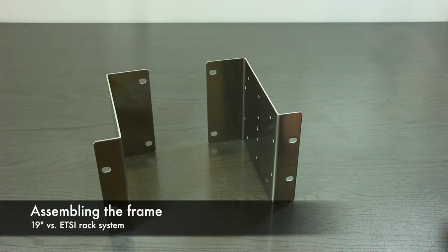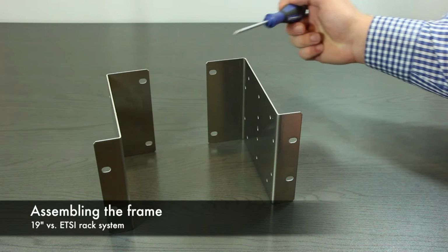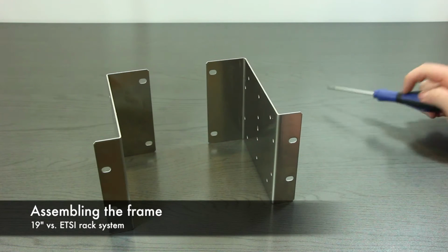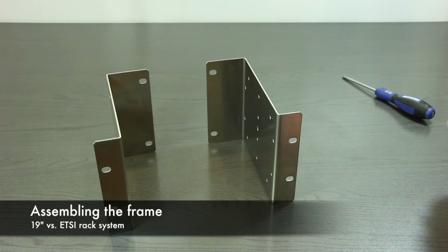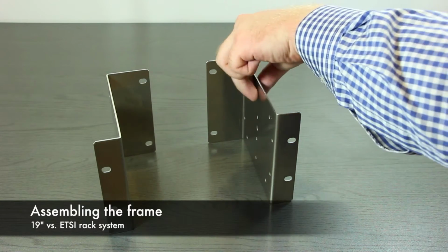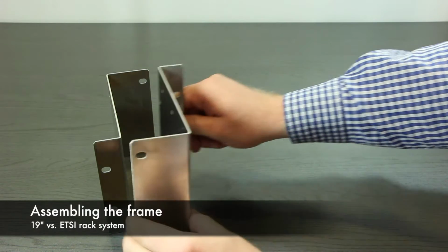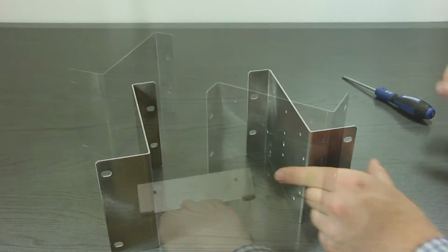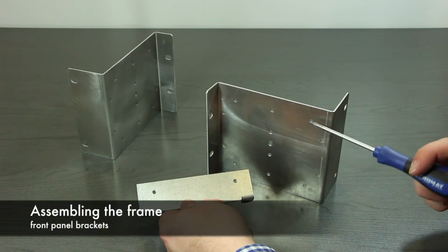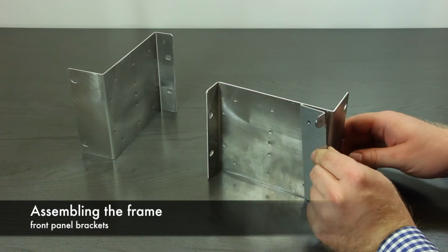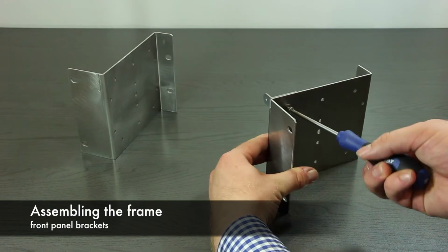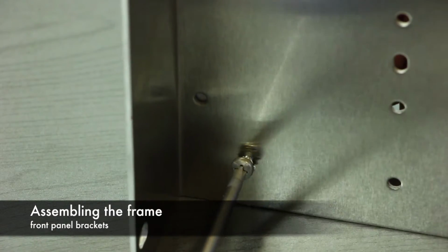For the 19-inch rack system, position the short legs of the rack brackets facing forward and the long legs facing the back. For the ETSI rack system, like in our case, position the long legs facing forward and the short legs facing the backside. With the right rack system in mind, we can begin with the assembly of the power rail frame. Attach the front panel bracket to the rack bracket by means of 2 screws and washers.